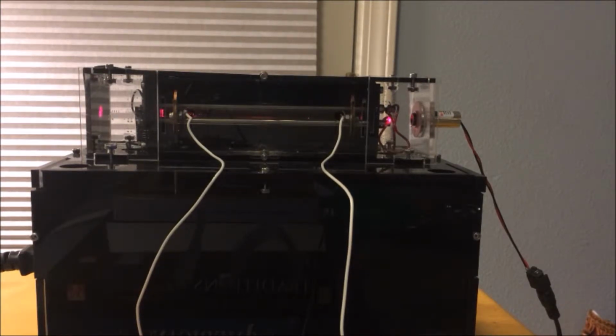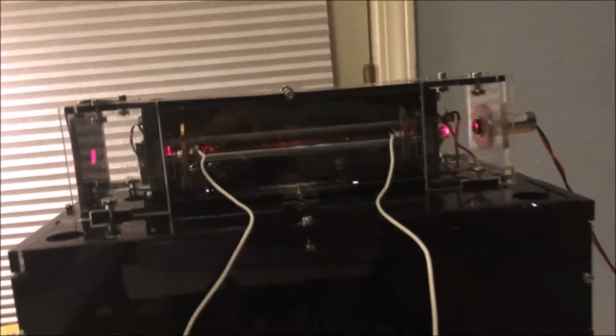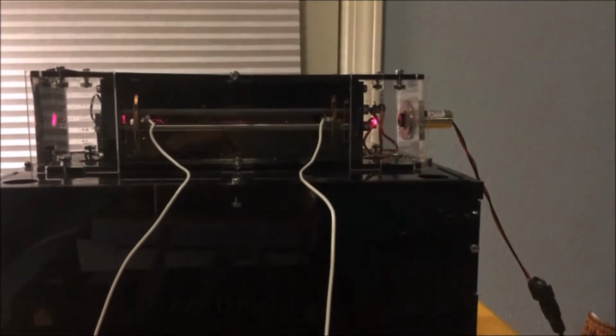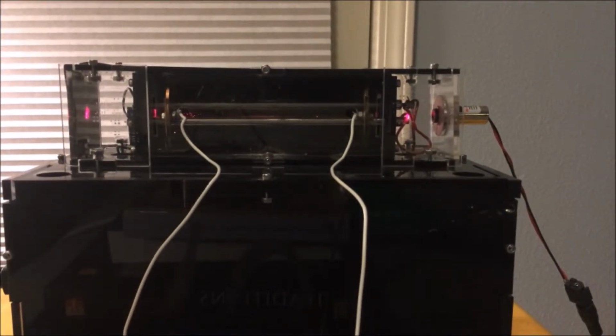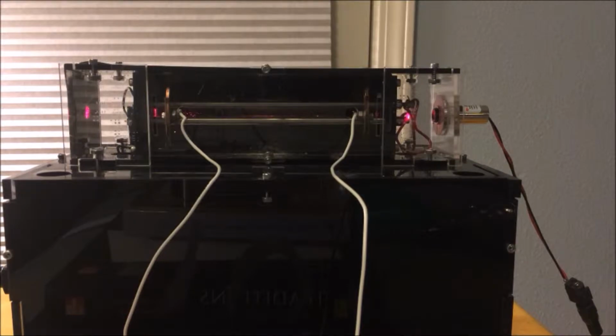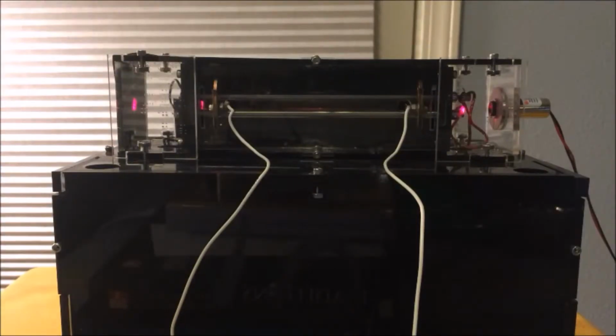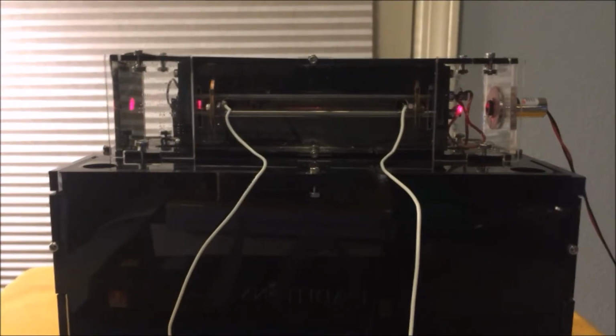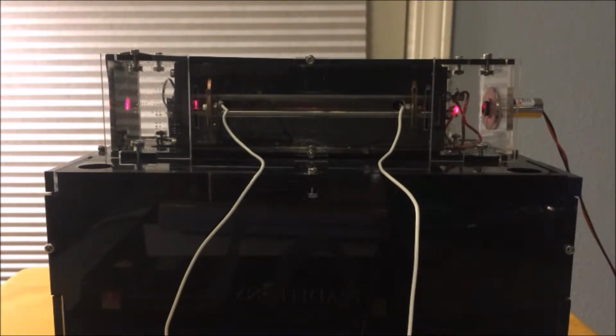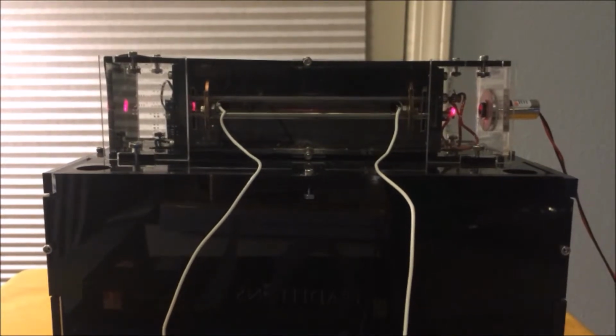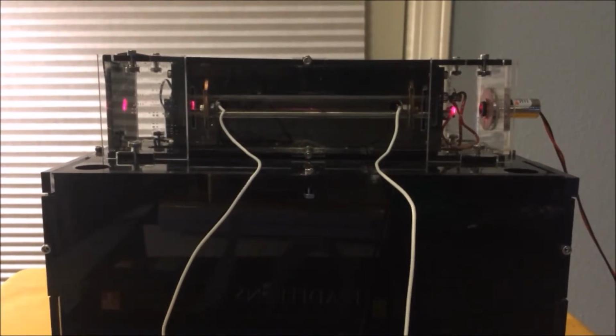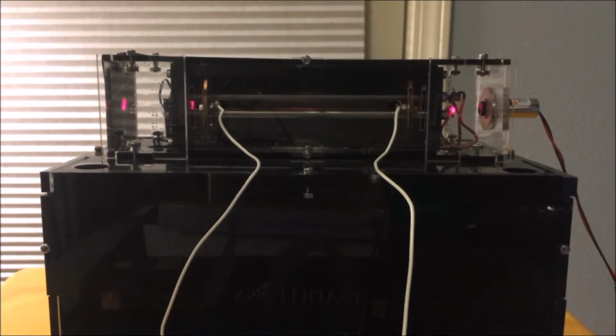And the high voltage is necessary because while the particles, if you look closely over here, seem very, very small, these particles still actually require a large amount of power to be able to be trapped against the force of gravity. So the trapping is best explained through an analogy to a saddle trap. So imagine you have a saddle on which you're trying to balance a ball. The shape of a conventional saddle has two opposite sides, which curve upwards, and the other two sides, which curve downwards.